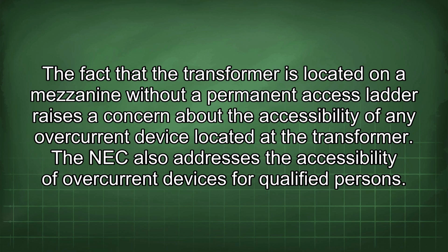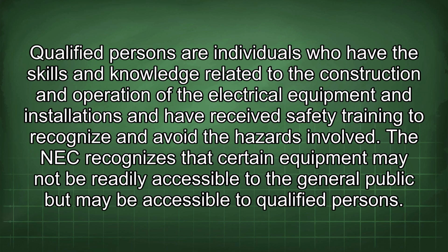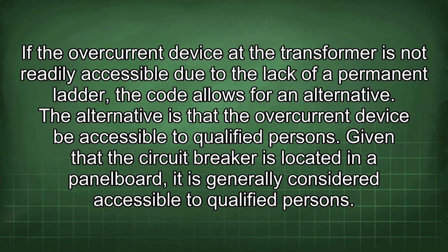The NEC also addresses the accessibility of overcurrent devices for qualified persons. Qualified persons are individuals who have the skills and knowledge related to the construction and operation of the electrical equipment and installations and have received safety training to recognize and avoid the hazards involved. The NEC recognizes that certain equipment may not be readily accessible to the general public but may be accessible to qualified persons. If the overcurrent device at the transformer is not readily accessible due to the lack of a permanent ladder, the code allows for an alternative. The alternative is that the overcurrent device be accessible to qualified persons.